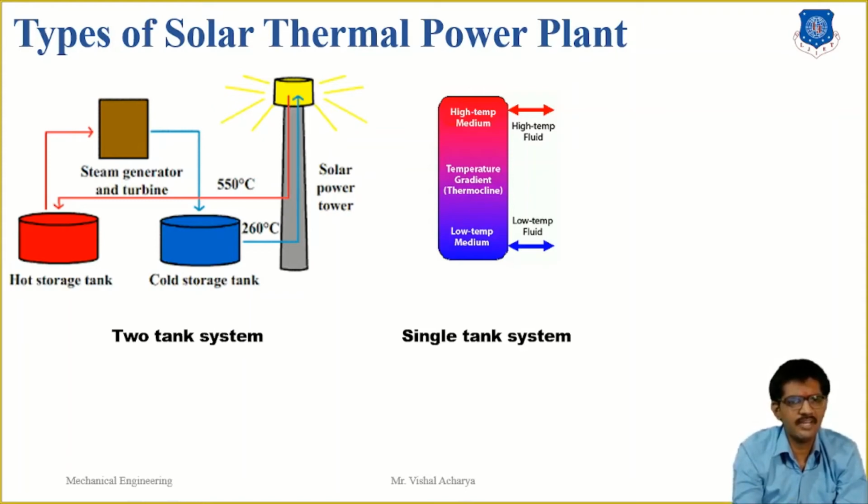A two tank indirect system functions the same way as a two tank direct system, except different fluids are used as the heat transfer and storage fluid. This system is used in plants in which the heat transfer fluid is very expensive or not suited for use as a storage material. The storage fluid from the low temperature tank flows to an extra heat exchanger, where it is heated by the high temperature heat transfer fluid.